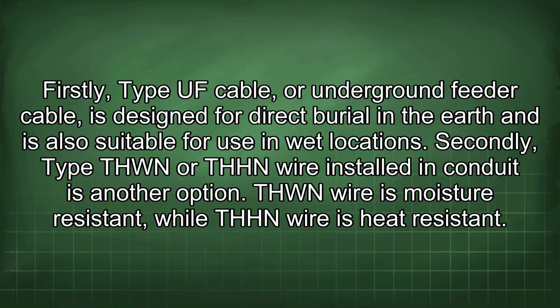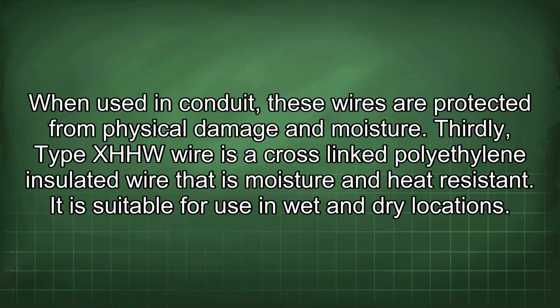Secondly, type THWN or THHN wire installed in conduit is another option. THWN wire is moisture resistant, while THHN wire is heat resistant. When used in conduit, these wires are protected from physical damage and moisture. Thirdly, type XHHW wire is a cross-linked polyethylene insulated wire that is moisture and heat resistant. It is suitable for use in wet and dry locations.